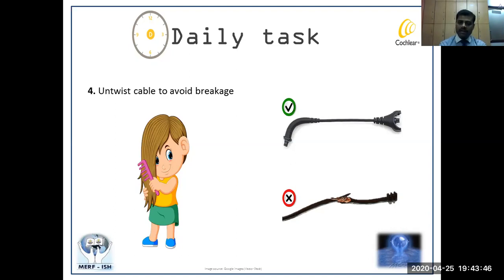Every day when the child comes home after school, you have to take out the cable, untwist it, and refix the cable on the processor. At night, before the child goes to bed, again untwist the cables and put it in your dry case or storage case. In the morning, before the child wears the device, make sure the cable is not twisted, untwist it and fix it. This is a very simple way of preventing your cable from being worn out so quickly.